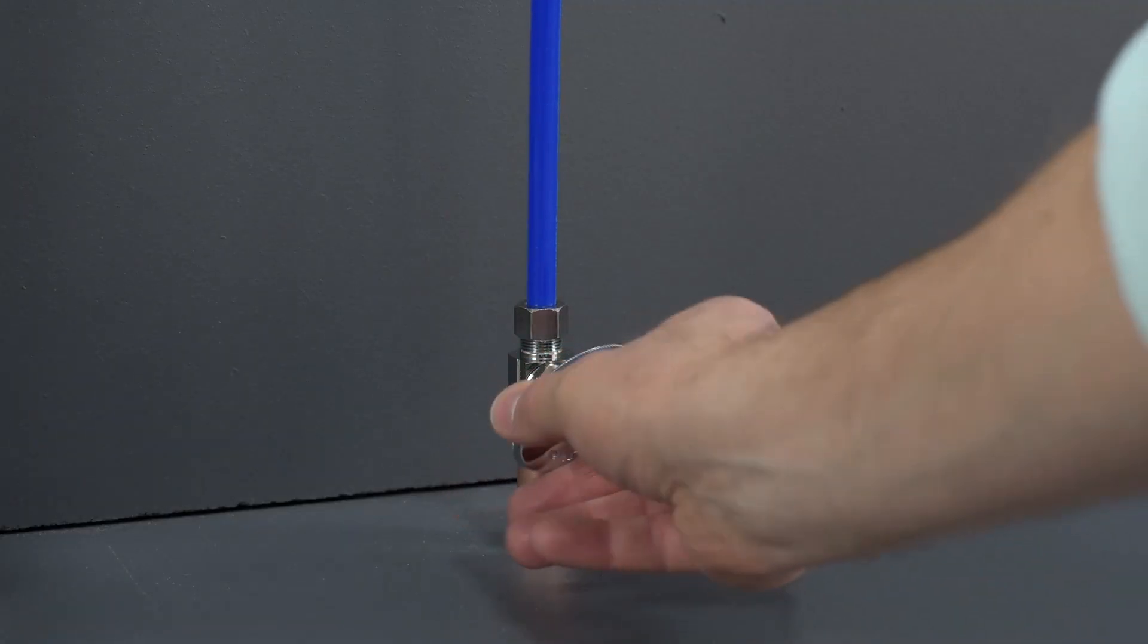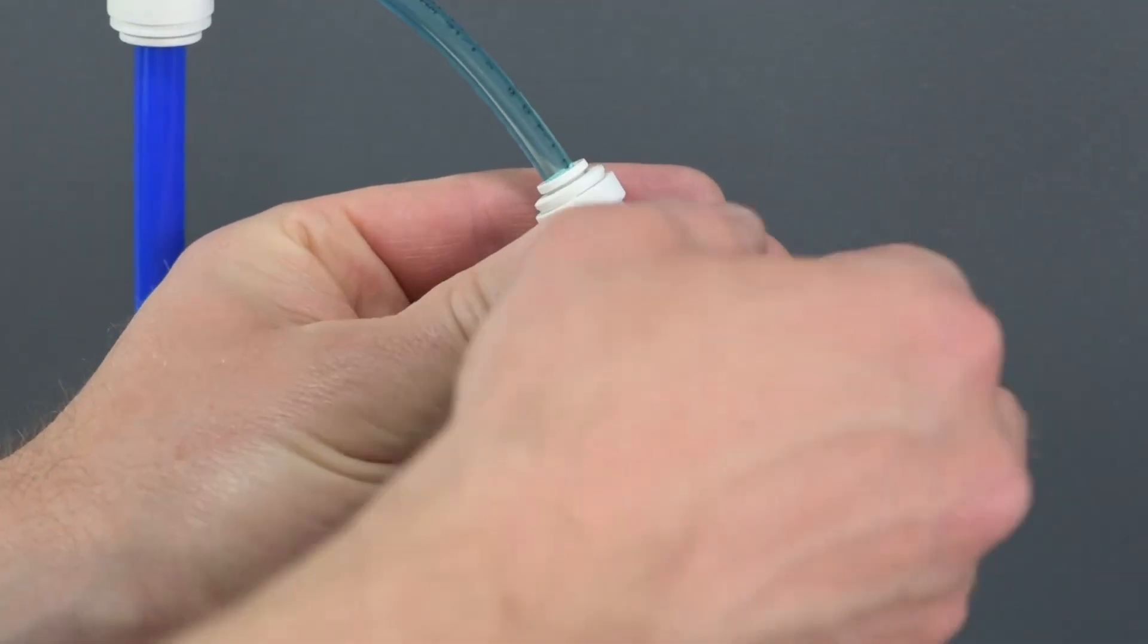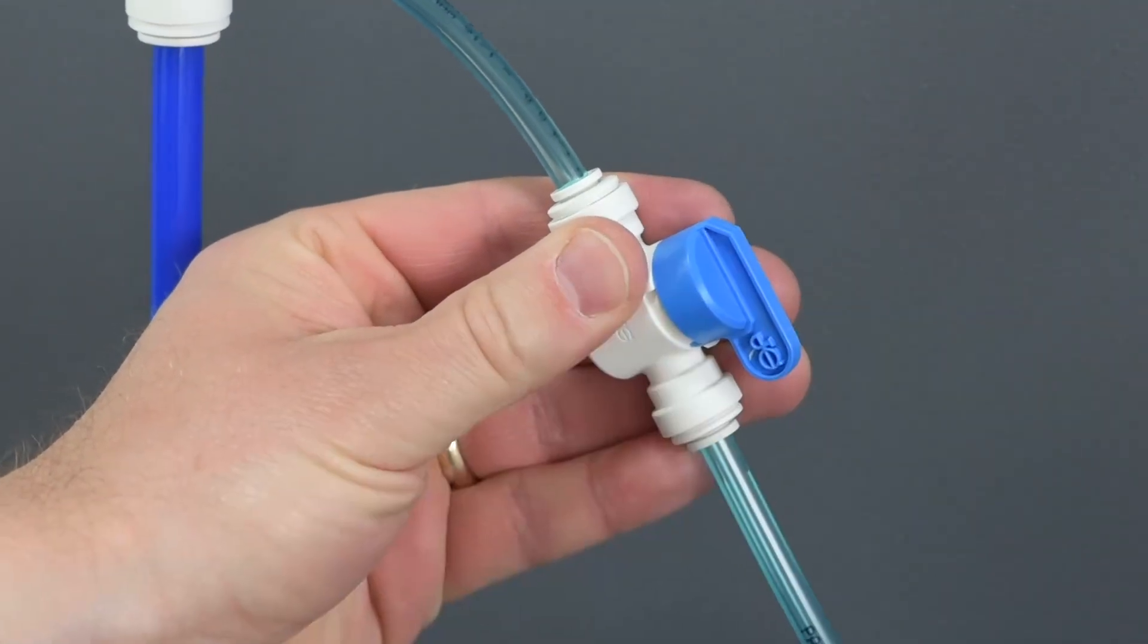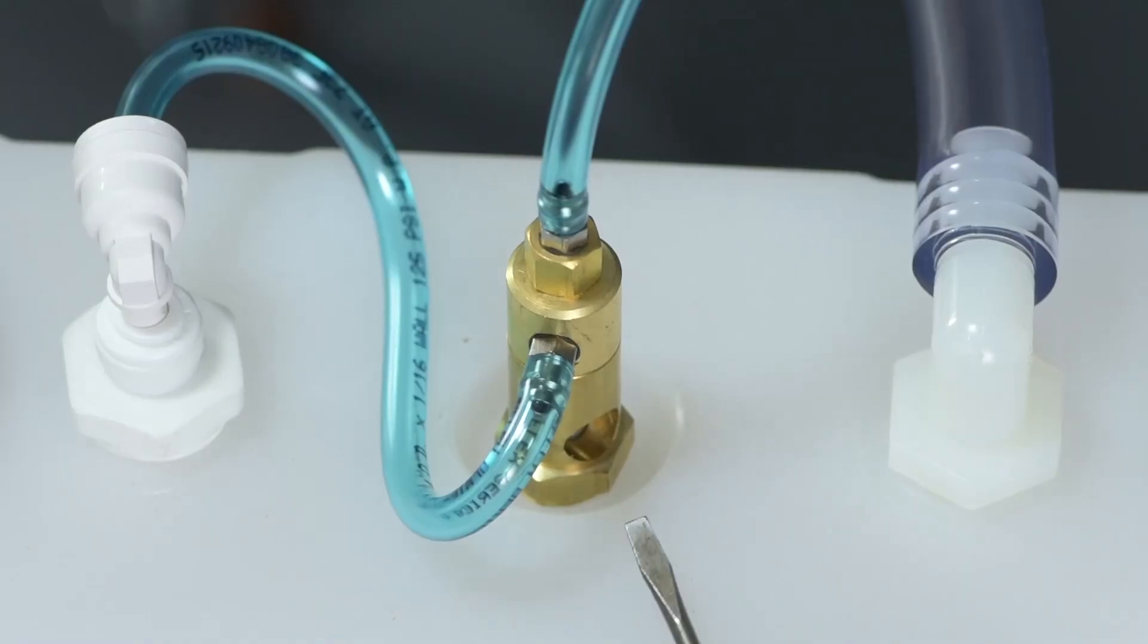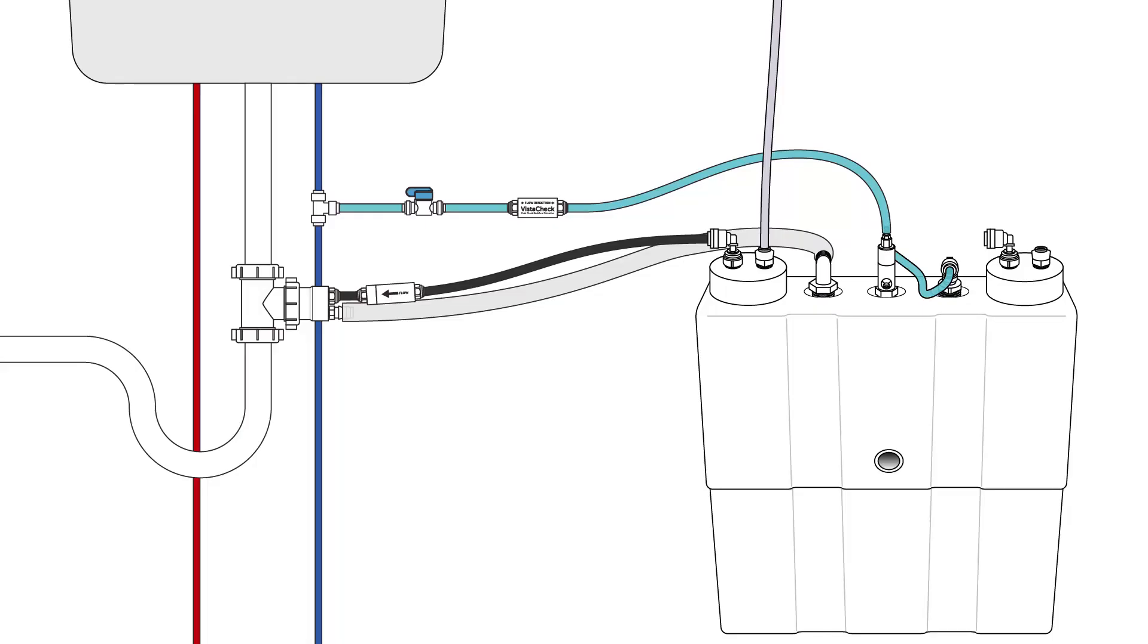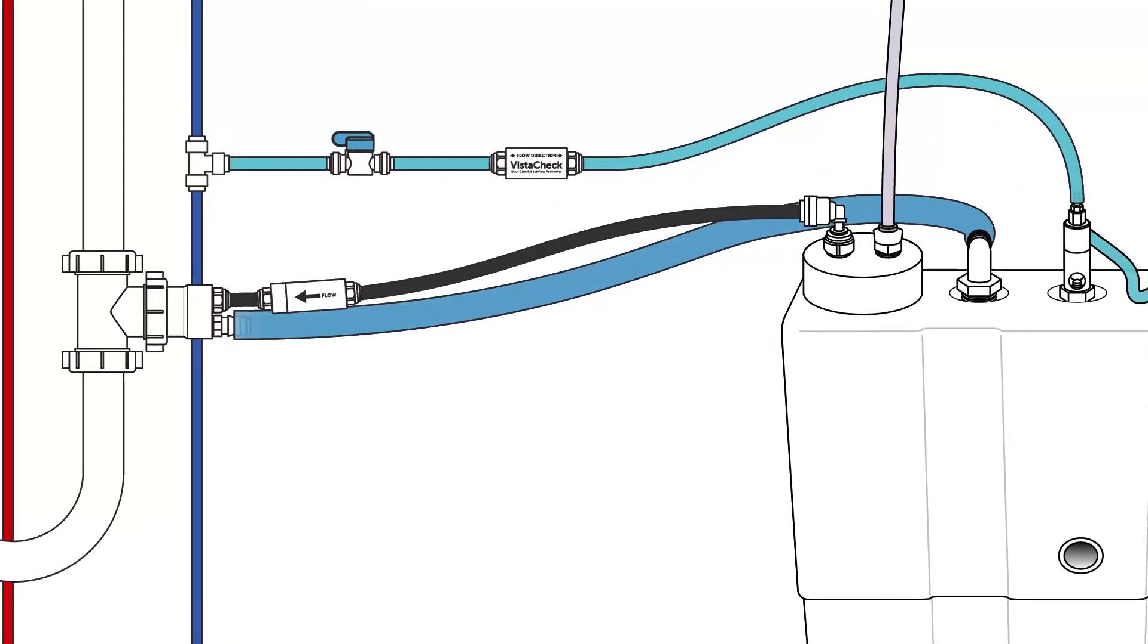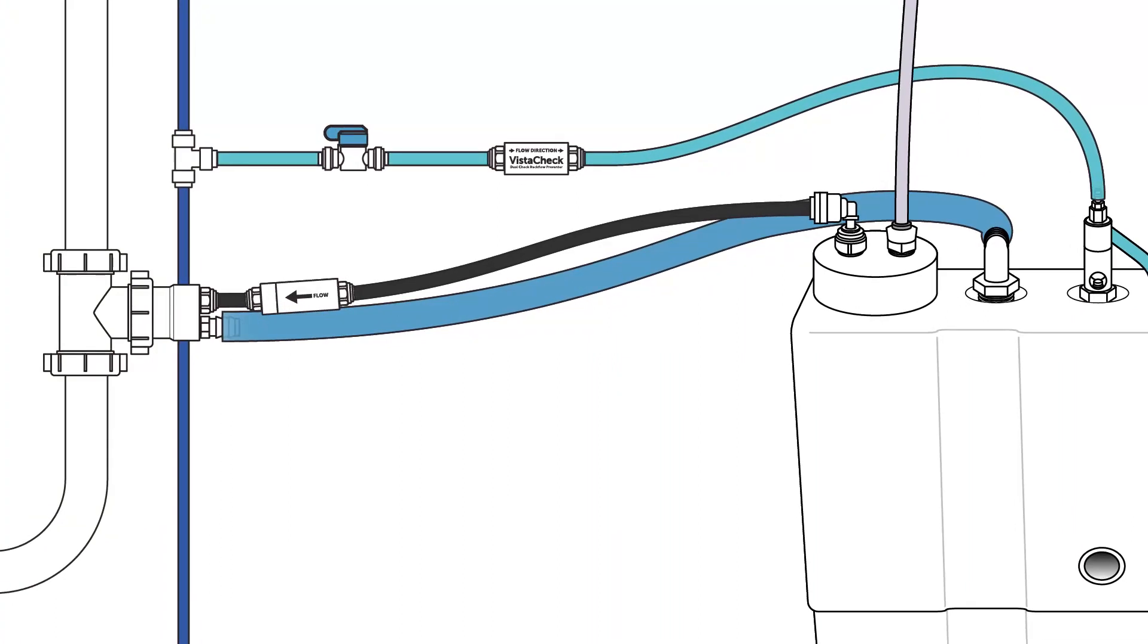Turn on the main water supply and check for leaks. Slowly open the inline water supply valve fully and check for leaks. Prime the system by inserting a small screwdriver in the viewport hole on the brass stem of the thermal regulator on top of the tank and pushing up on the water valve piston. The system is primed when water can be seen leaving the half inch overflow fitting on the tank and running to the drain adapter.